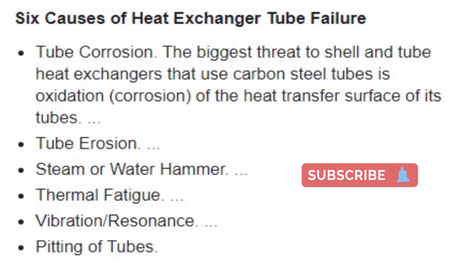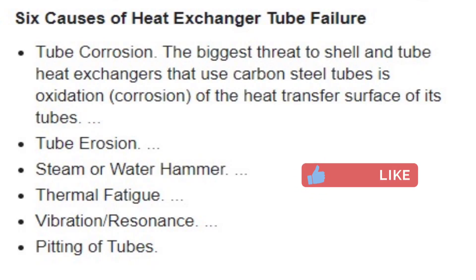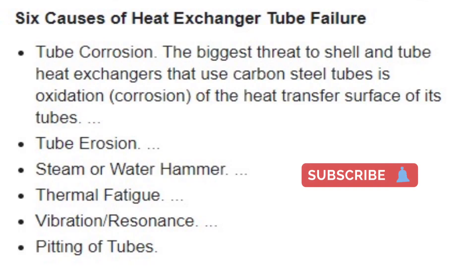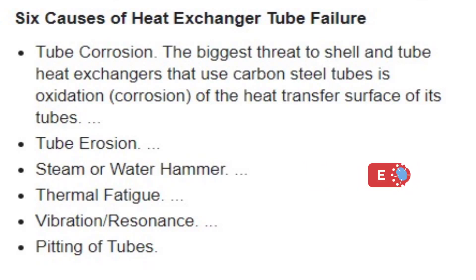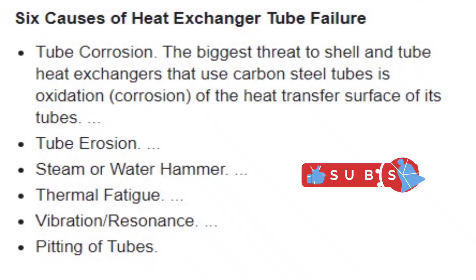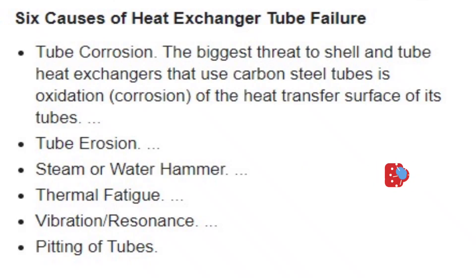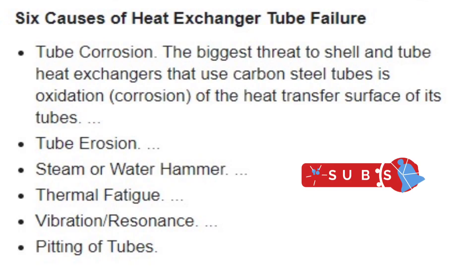Thermal fatigue occurs when extreme temperature differences between the shell and tubes result in tube flexing. Vibration and resonance from whatever source, whether induced externally or internally, can impose powerful forces on heat exchanger tubes. Once vibration or resonance commences, it can increase in intensity to a point where tubes rupture and fail, or lose their seal with the tube sheet and leak.